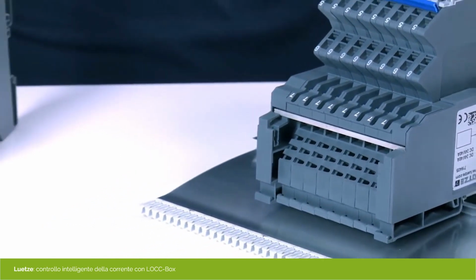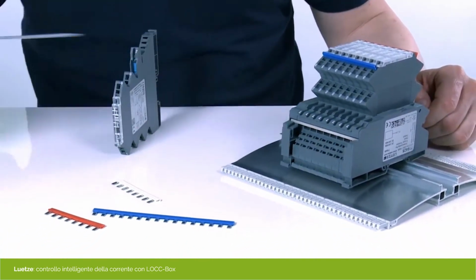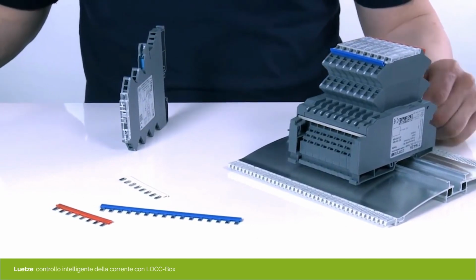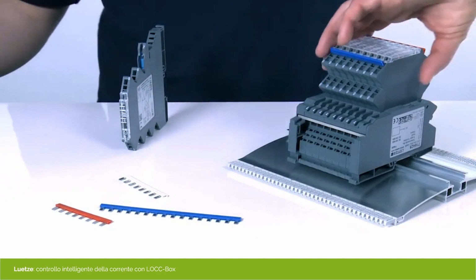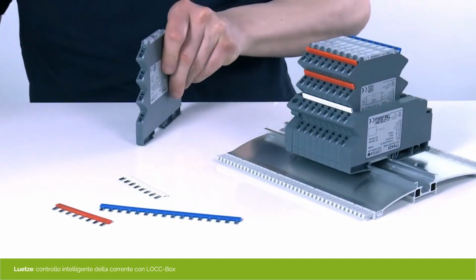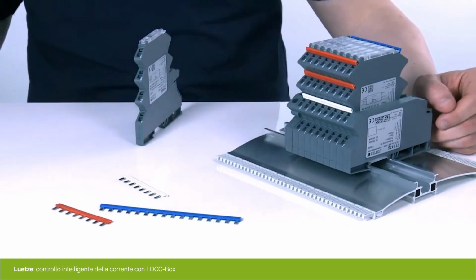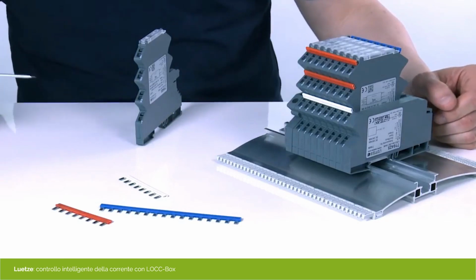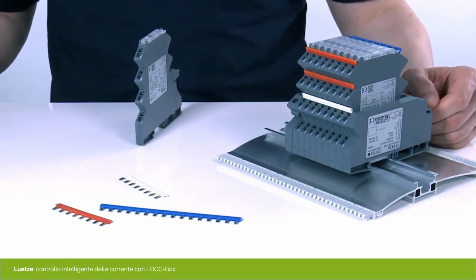The electronic ground is made available to the module on terminal 5. In the case of several modules, this is only required once. The other modules can be connected easily with a jumper COM. The load is connected on protected terminal 1. The remote input, terminal 2, allows targeted activation and deactivation, and a reset at any time.